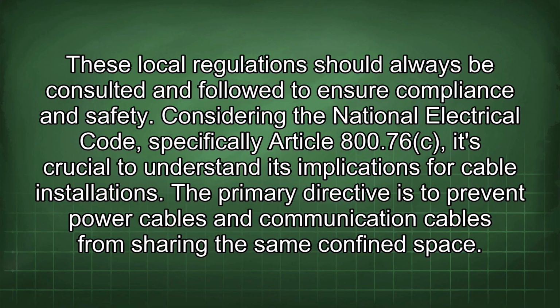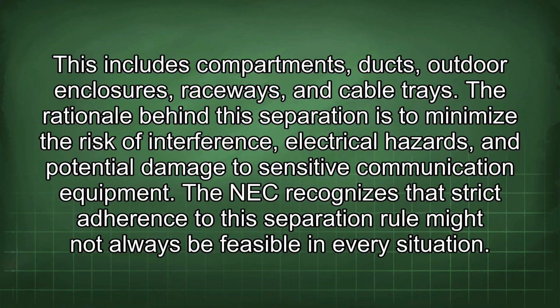Considering the National Electrical Code, specifically Article 800.76, it's crucial to understand its implications for cable installations. The primary directive is to prevent power cables and communication cables from sharing the same confined space. This includes compartments, ducts, outdoor enclosures, raceways, and cable trays. The rationale behind this separation is to minimize the risk of interference, electrical hazards, and potential damage to sensitive communication equipment. The NEC recognizes that strict adherence to this separation rule might not always be feasible in every situation.